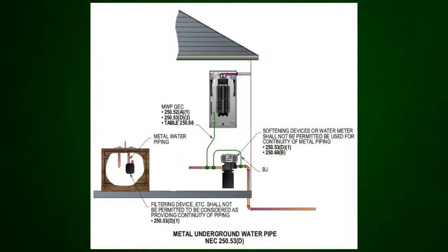Yeah, and what I like about that, go back to that illustration really quick. There's a lot of confusion around, and this might be another myth, that the grounding electrode conductor needs to be continuous. Well, you're showing it in that picture as continuous. It's electrically continuous. Mm-hmm. So it doesn't mean the wire has to be just one piece. A lot of people get confused on that, and so I really like how you did that in your illustration, because that is considered electrically continuous, even though it's not one piece of wire. So I just wanted to add that in there because that's a good illustration. I like how you did that to where it's required to be electrically continuous, not mechanically continuous.